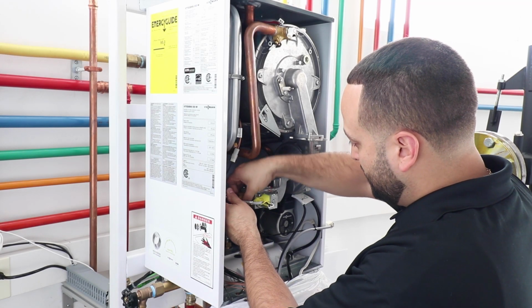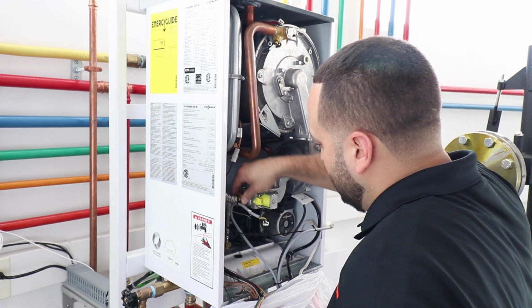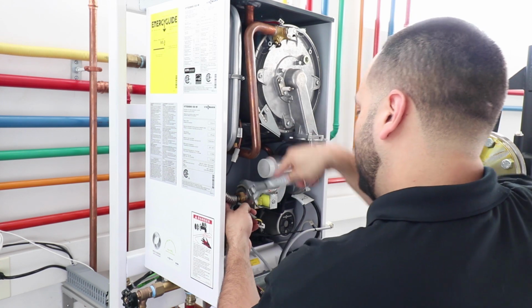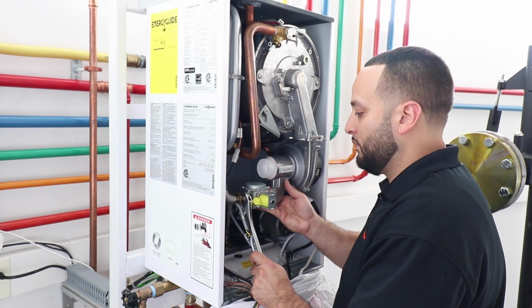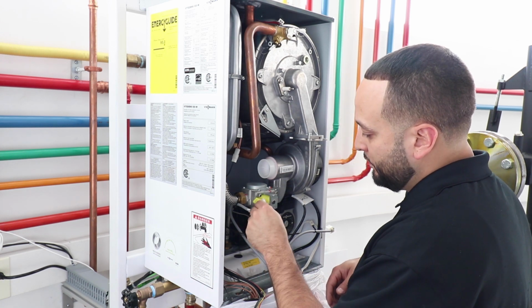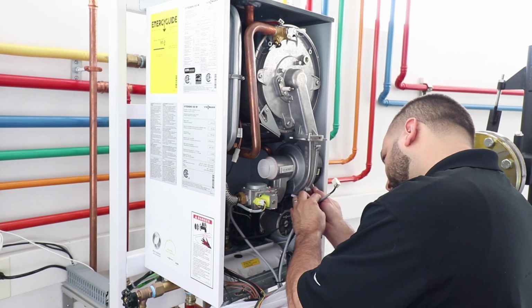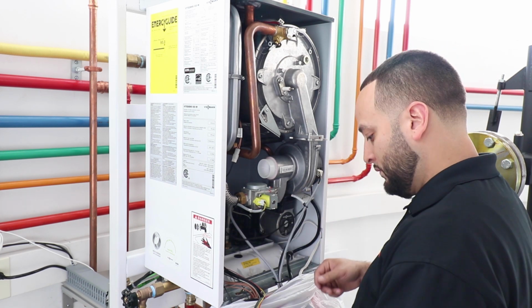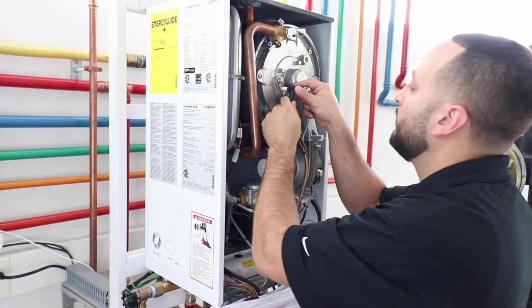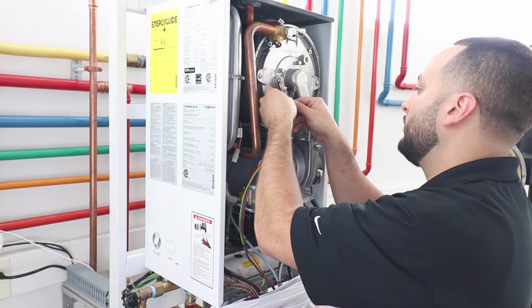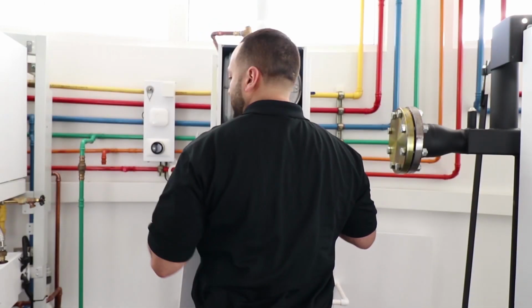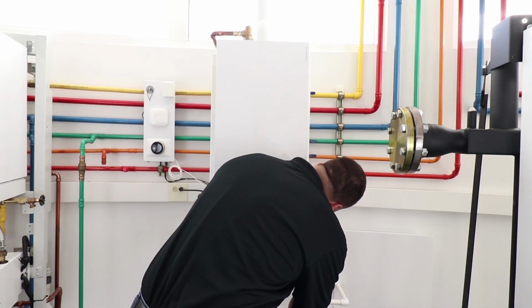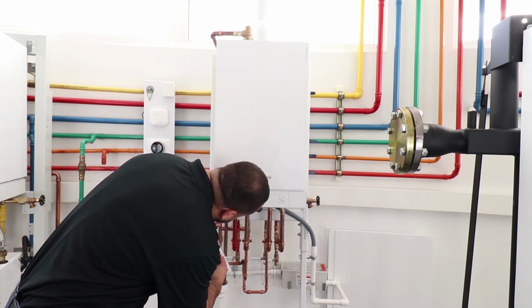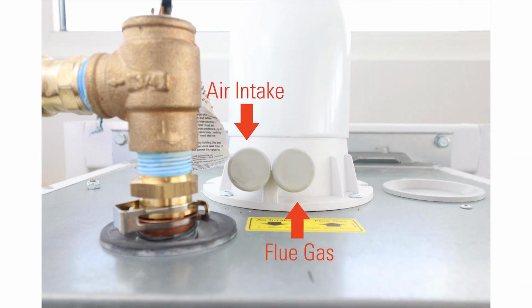Reinstall fuel connection pipe and gasket as well as all electrical connectors. Be sure to clean and flush the condensate trap. Once service has been completed, perform a combustion analysis utilizing the flue port on the vent pipe adapter located on top of the boiler.